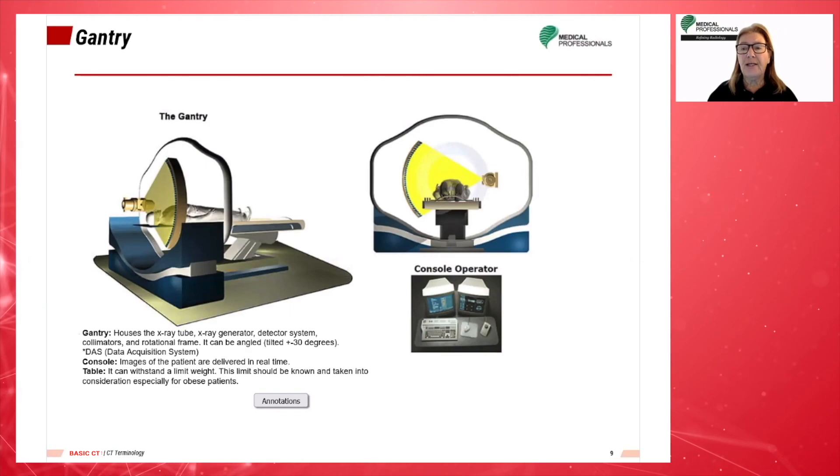The gantry is a mounted framework that surrounds the patient. The gantry houses the x-ray tube, the x-ray generator, the detector systems, collimators, and the rotational frame, all of which are considered the imaging components. Two important features of the gantry are the gantry tilting range and the gantry aperture. The gantry can be tilted plus or minus 30 degrees. Most scanners have a 70 cm aperture. The table slides into and out of the gantry during a CT examination.